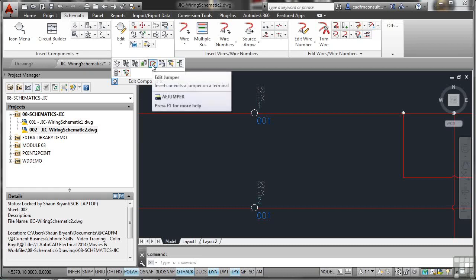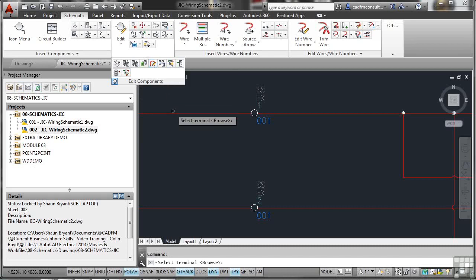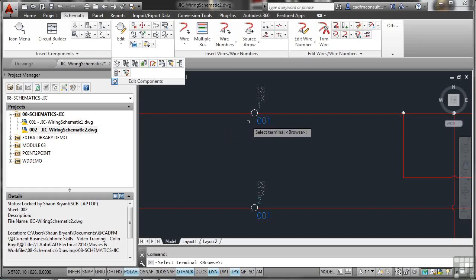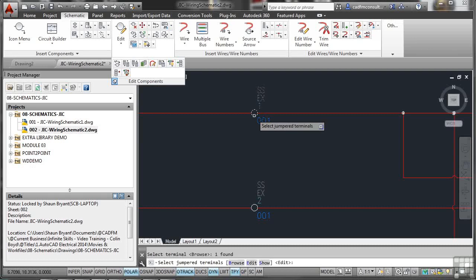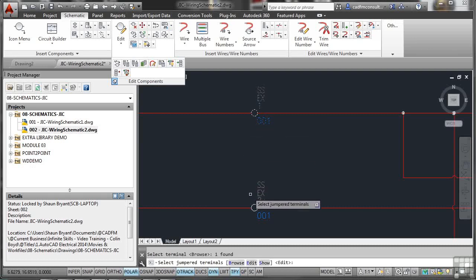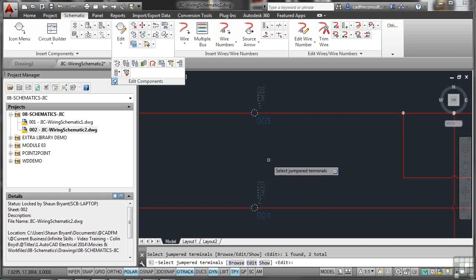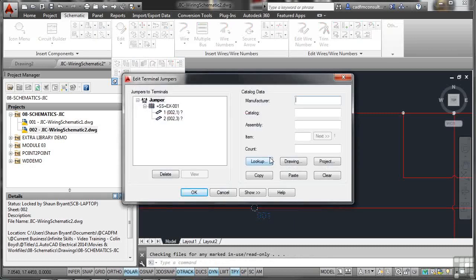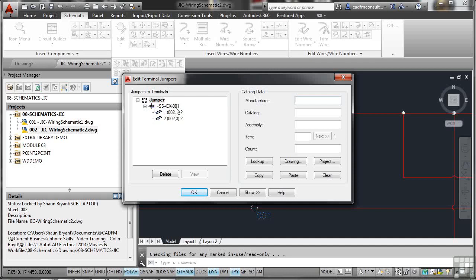There is a jumper setting here. Edit jumper. So, that inserts or edits a jumper on a terminal. Now, we don't have any jumpers yet. So, if I click there, it'll ask me to select a terminal or I can go and browse. Well, my terminal's right there. That's easy. I can select that one there and select the jumper terminals there. So, I want that one there. So, I'm going to add a jumper to those and then press enter to confirm. As soon as I do that, you'll see that there are jumpers now added. There's the location and so on. S-S-E-X-001. And as you can see, there's two jumpers there, but there's question marks right now. That's because we haven't linked them to anything else. There's no parent-sibling-parent-child relationship. Hence, the question marks.